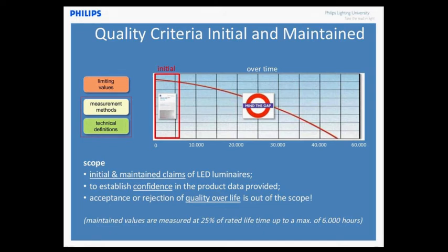What you will see is that the IEC document focuses mainly on initial and maintained claims, because they take into account a period of 6,000 hours - that's why they call it maintained. But the only objective is to establish confidence in the data provided by the luminaire manufacturer. At this moment, quality over time or quality over life is not in the scope of the international standard. The most important reason is that there are still too many things uncertain. The technology is quite young and we simply can't oversee, when you bring a product to market with an expected life of 10, 15, maybe 20 years, what will happen over that time. But you will find an informative annex that gives guidance on how you should look at lifetime metrics over time.